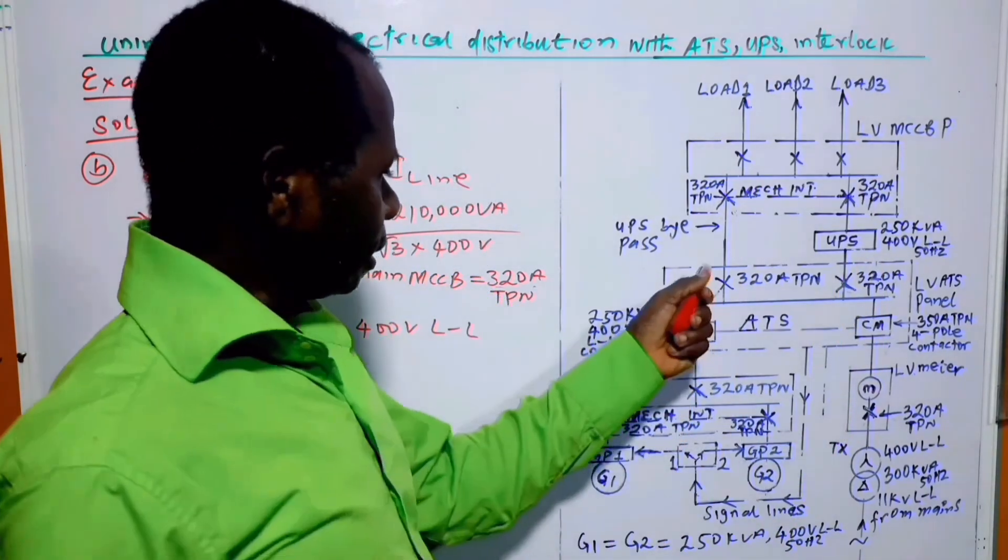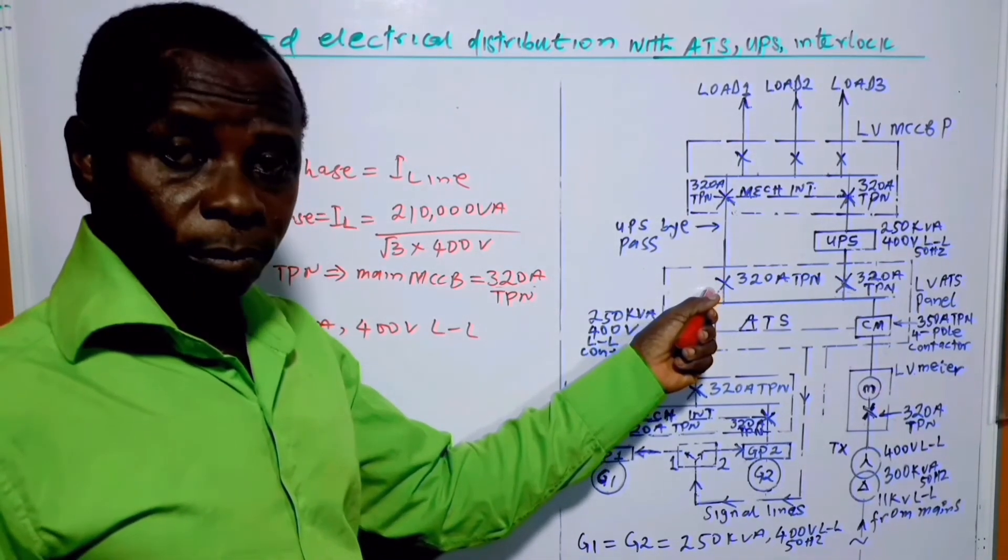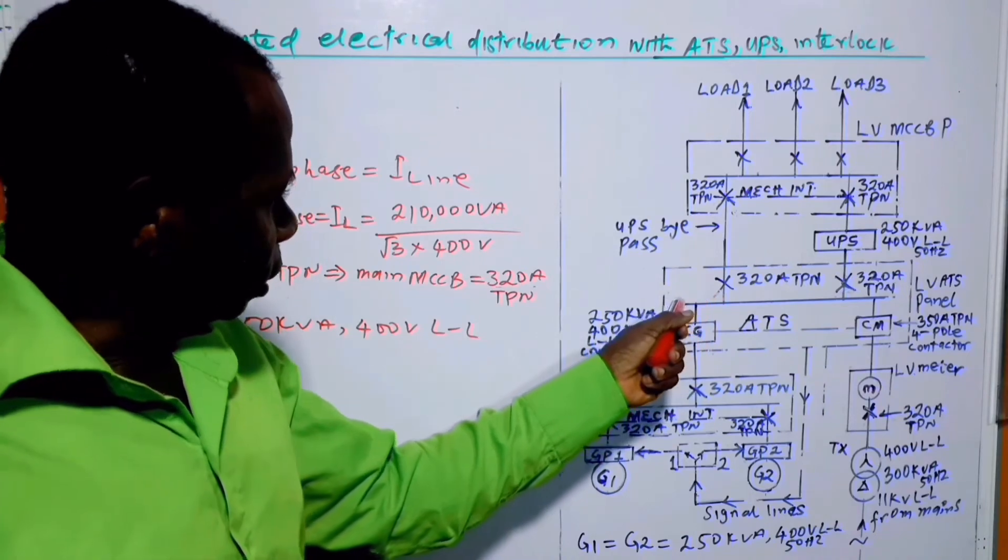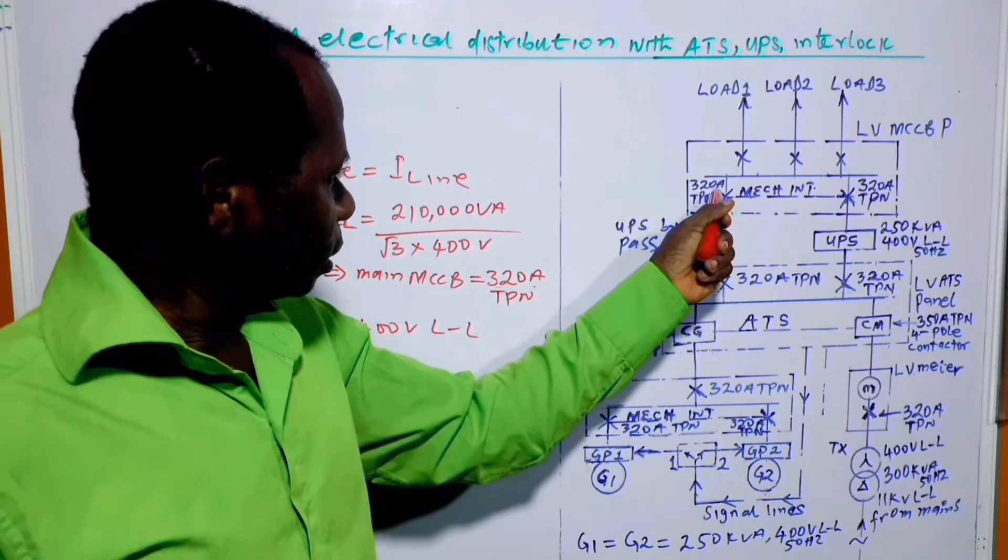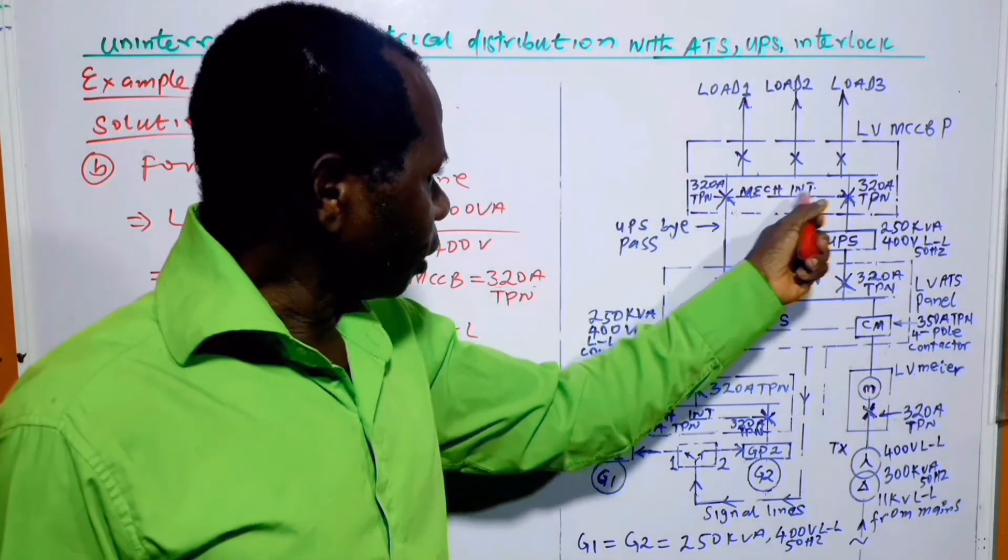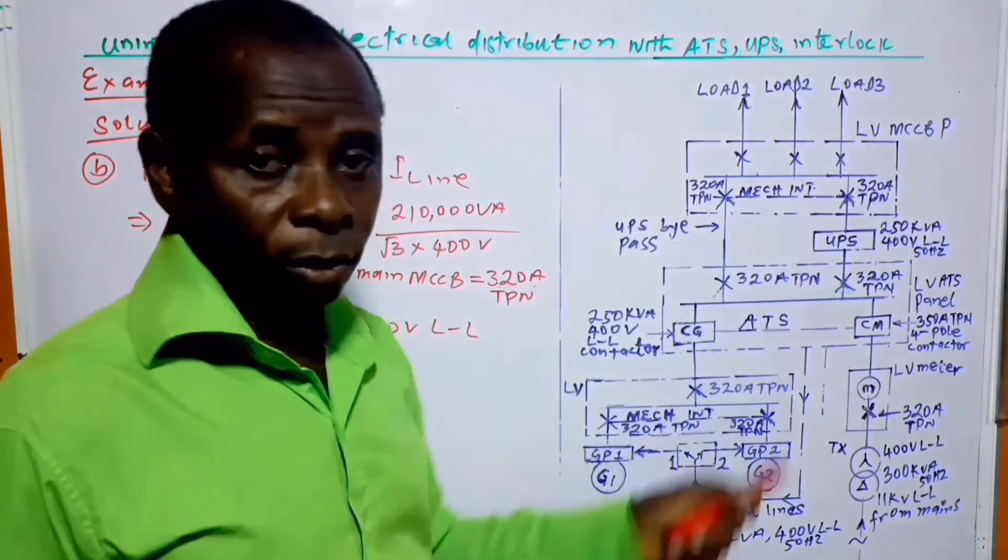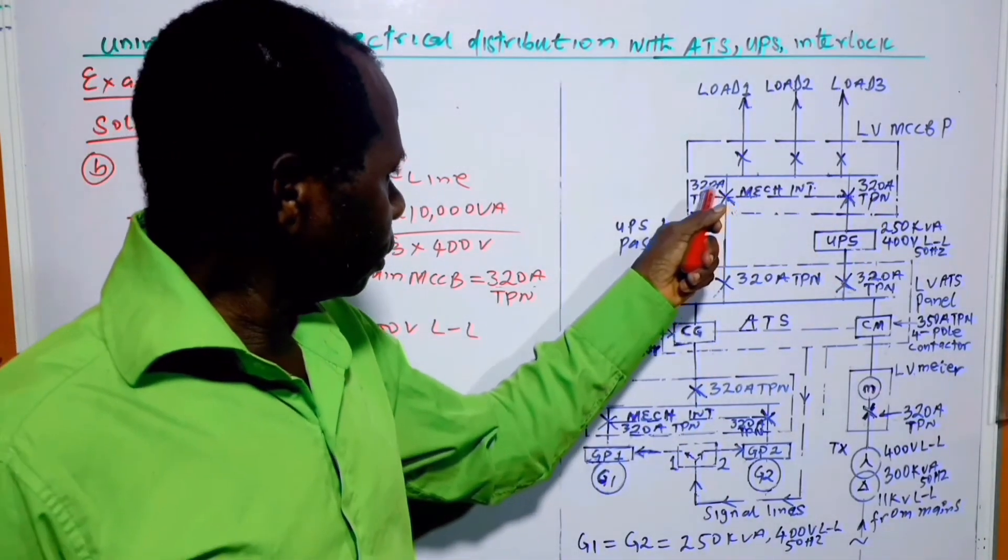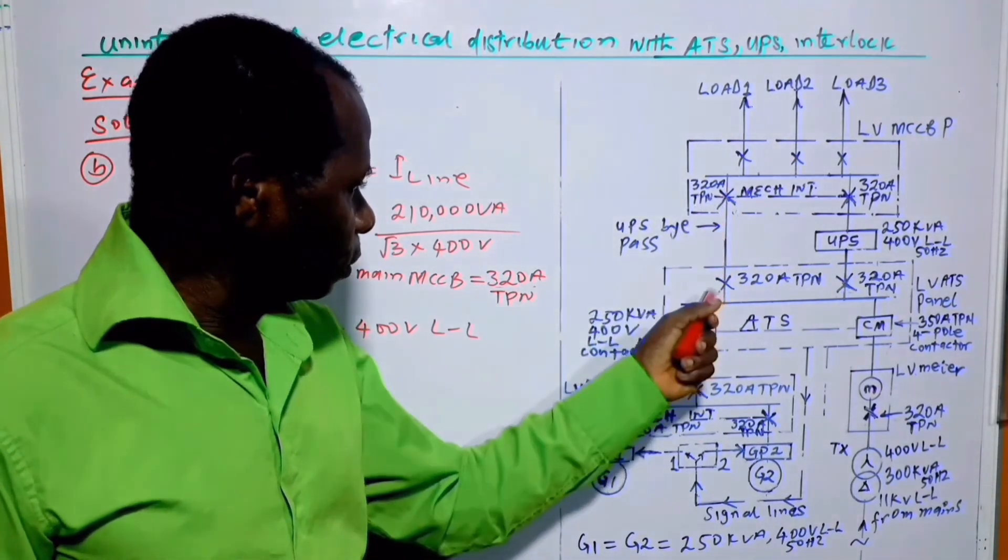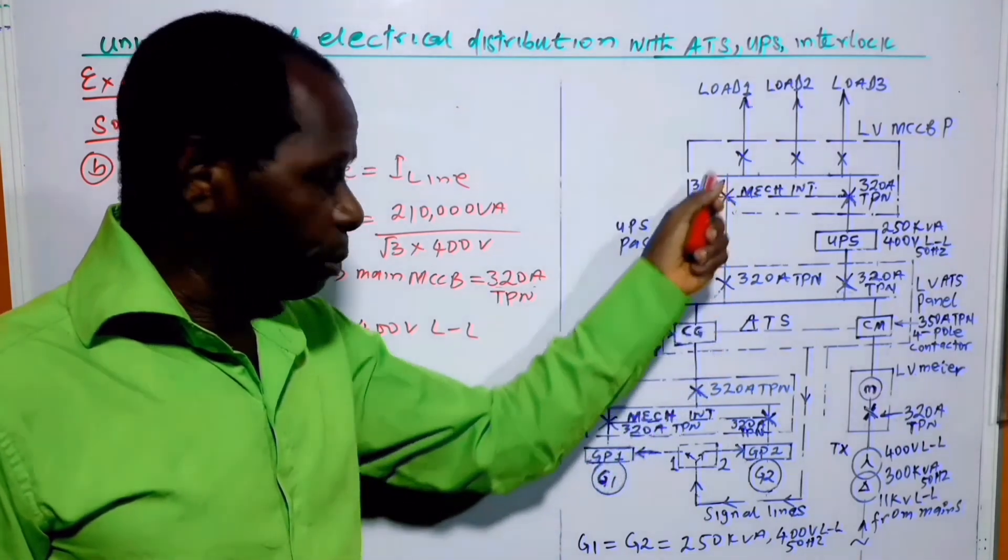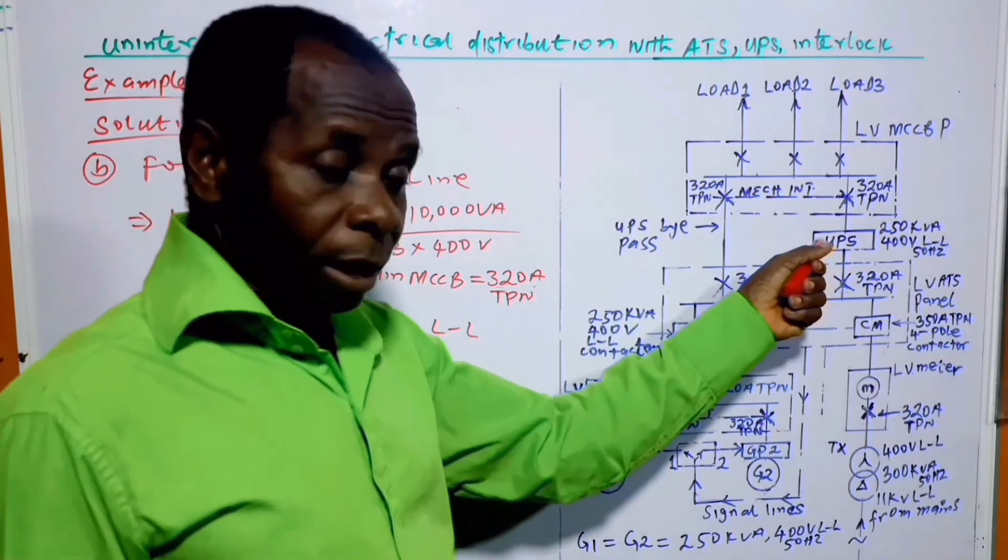Because normally, this circuit breaker here is left open. Because it is serving a different purpose. The interlock is adjusted such that it is only this circuit breaker that closes. This one opens. This one also opens. The interlock is such that these two circuit breakers become functional when the UPS has problem.